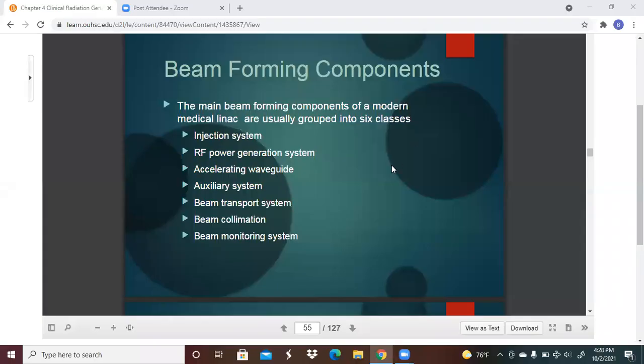All right, so what are the beam forming components of this linear accelerator? The main beam forming components of a modern Linac are grouped into 6 classes. You've got the injection system, RF power generation system, accelerating waveguide, auxiliary system, and beam transport, beam collimation, and beam monitoring system. Boy, that looks like 7 components, doesn't it?